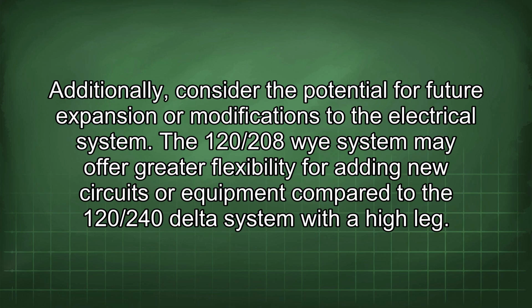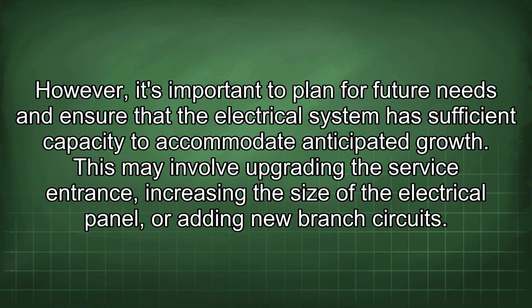Additionally, consider the potential for future expansion or modifications to the electrical system. The 120/208Y system may offer greater flexibility for adding new circuits or equipment compared to the 120/240 delta system with a high leg. However, it's important to plan for future needs and ensure that the electrical system has sufficient capacity to accommodate anticipated growth. This may involve upgrading the service entrance, increasing the size of the electrical panel, or adding new branch circuits.